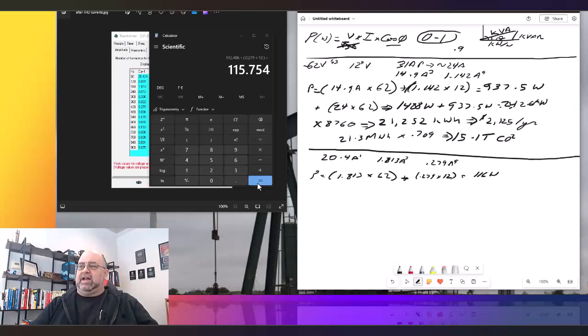Now we're going to take that and let's add this 20.4 times 62. So what happened to our peak? Well, it's coming down as well because we don't have all that harmonic there, so less loading from the triplen harmonic. So it had a direct impact on peak current, going from 31 down to 20, 20.4 to be exact. So about a 6 amp drop from that load, basically.